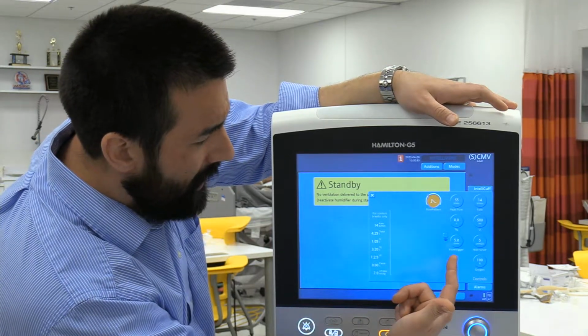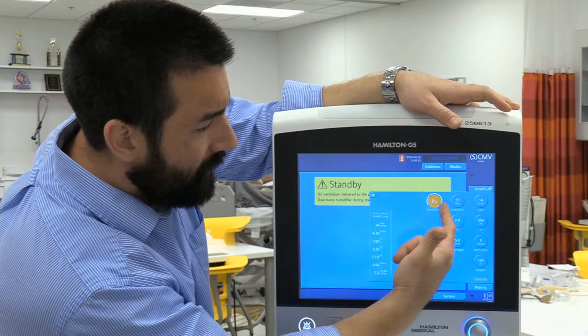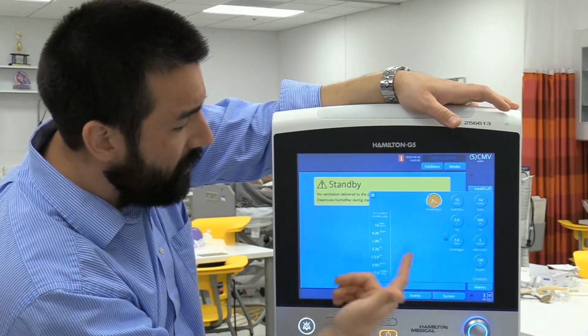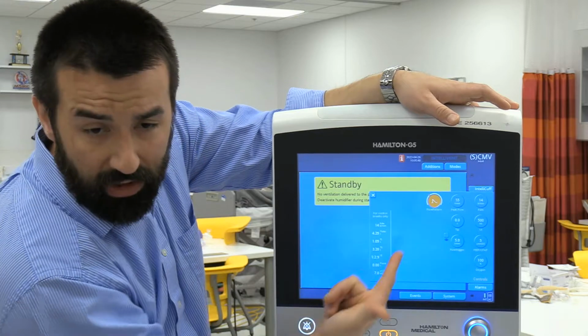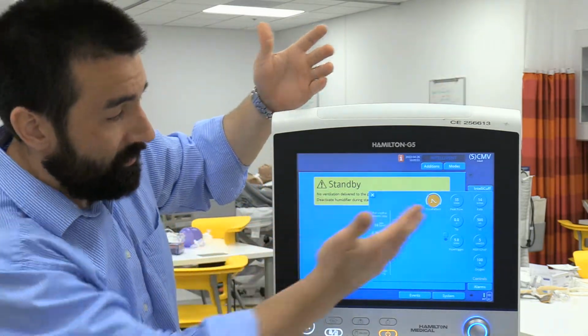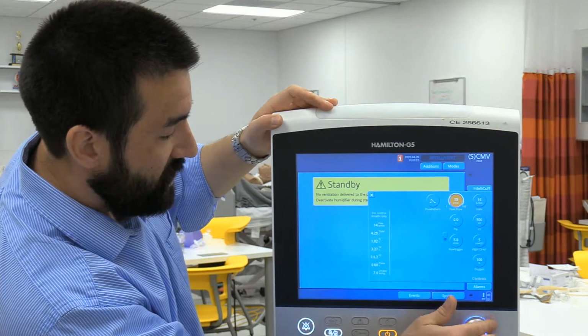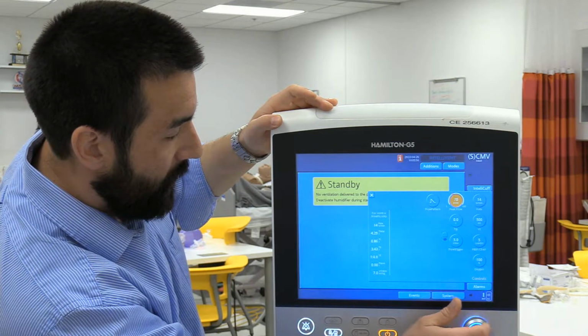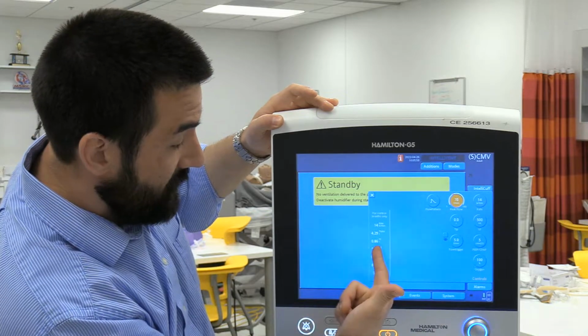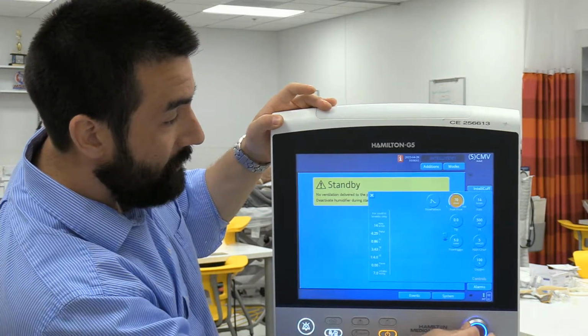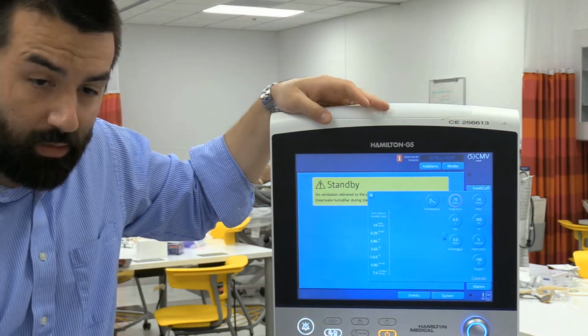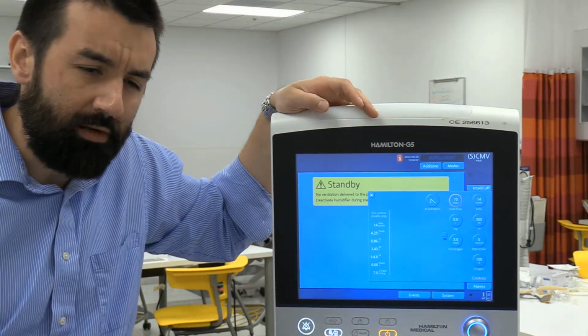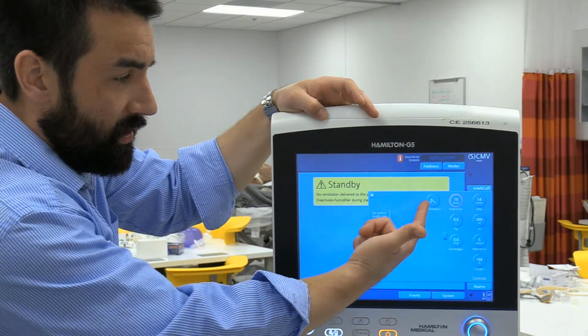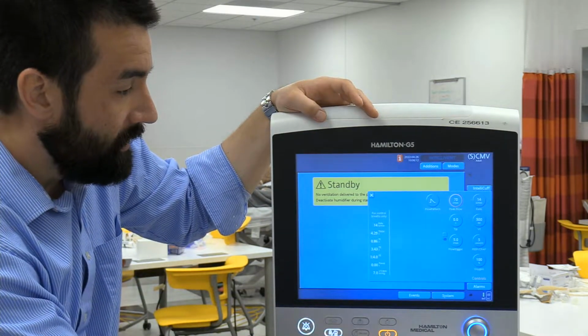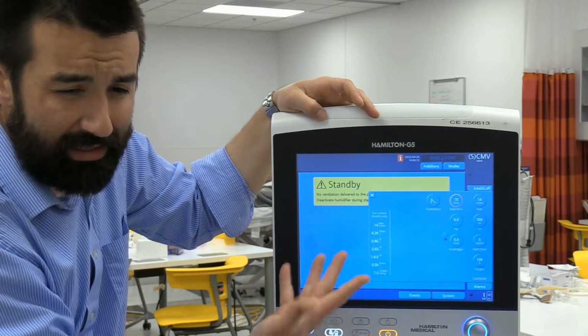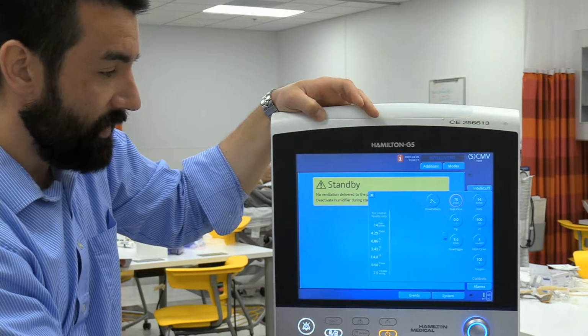If you're looking and the patient is needing a lot of flow and is flow hungry up front, but my I time ends up too short, you can change this and maintain a longer I time even with a higher flow rate. So I'm going to adjust this again and try to get us back down to our 0.8. You can see with this, I can give a peak flow of 70 and still have a 0.86 I time. So don't fixate on that too much. I just want you to know it's an option. If you're having too long of an I time and can't figure it out, you might be in the exponential decay and not fully aware of that. You also have sine wave and square flow waveforms. We'll talk about that later on.